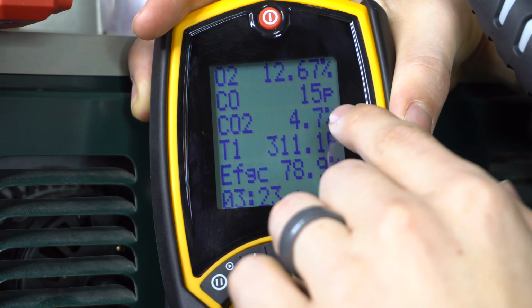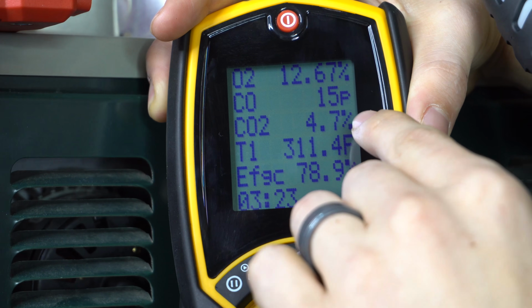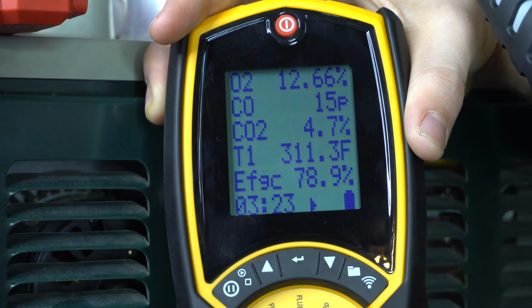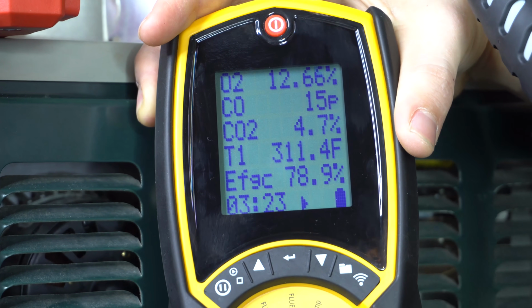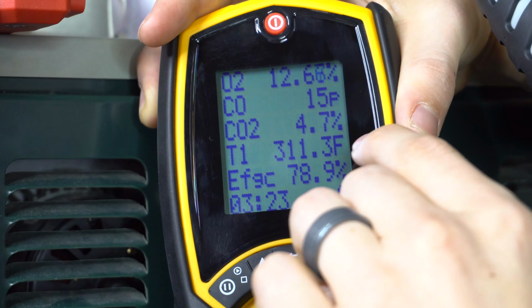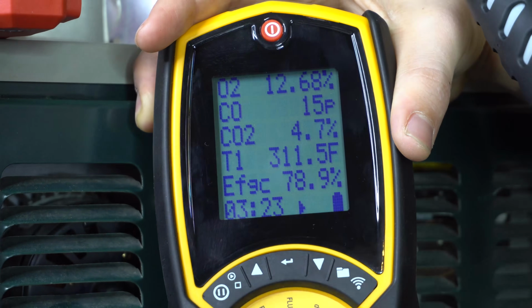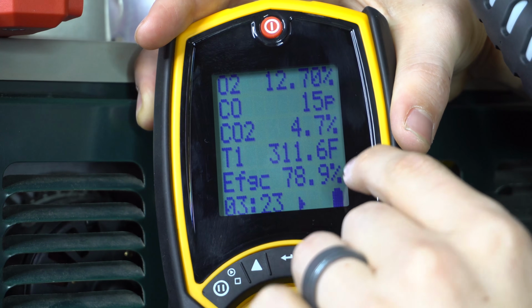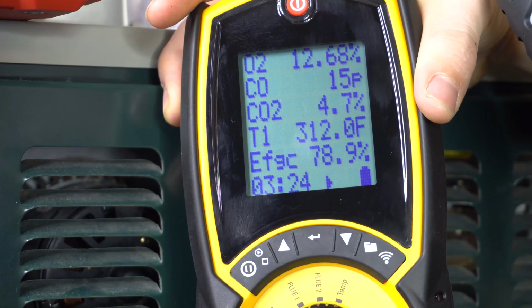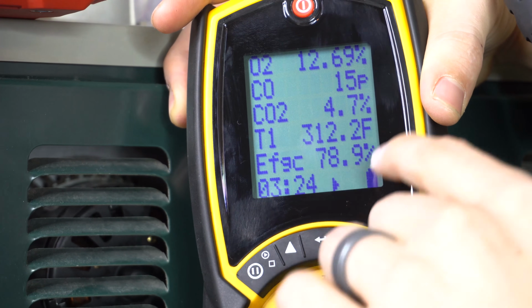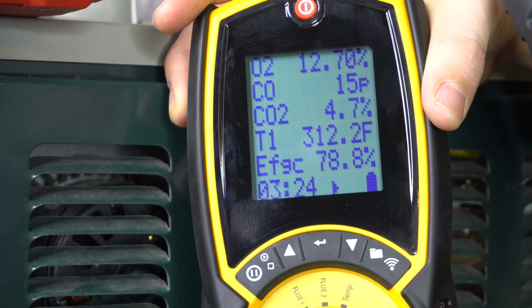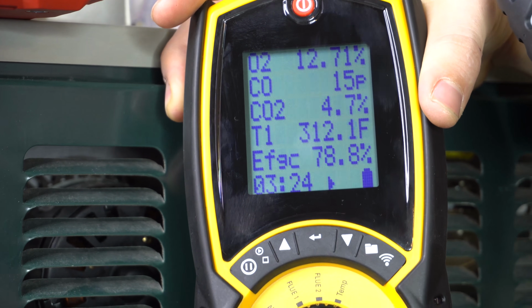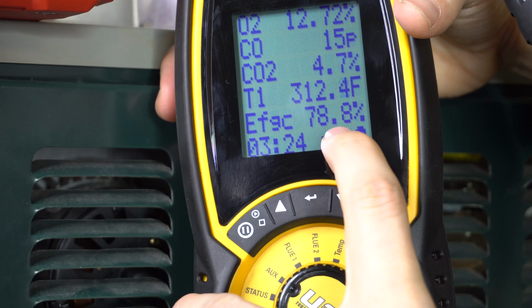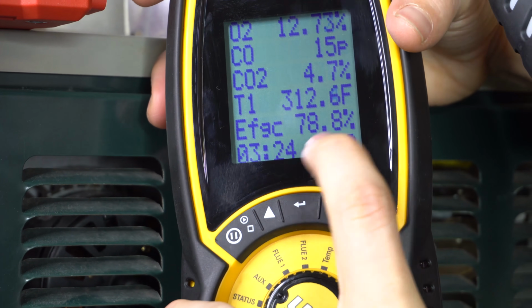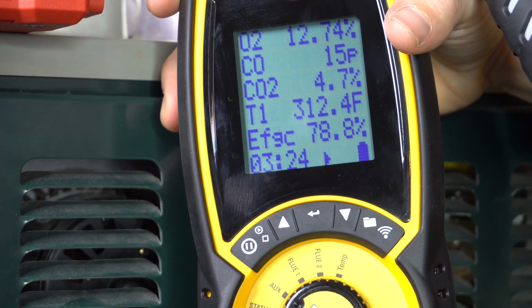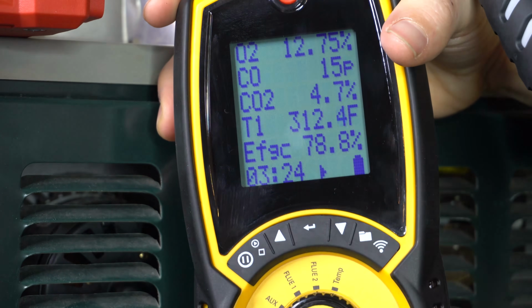Carbon dioxide is typically between 4 to 8% is what I see. It's on the lower side, which is good. That just means it's burning clean. And my stack temperature, or my exhaust pipe temperature, is steadily climbing, which is normal as well. For an 80% furnace, around 300 degrees inside of the exhaust pipe, that's a pretty normal reading. And my efficiency calculation is at about 78.8%. And being that it's an 80% furnace, that's actually pretty good.